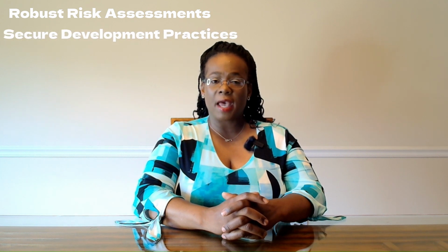Recently, the FDA issued final guidance titled Cybersecurity in Medical Devices: Quality System Considerations and Content of Premarket Submissions, which incorporates recommendations related to Section 524B of the FD&C Act, superseding the previous guidance from 2023. This means the FDA now requires robust cybersecurity measures integrated into your medical device development lifecycle. This includes robust risk assessments, secure development practices, and detailed documentation in your pre-market submissions. Furthermore, the FDA continues to emphasize the importance of post-market management of cybersecurity vulnerabilities throughout the lifecycle.